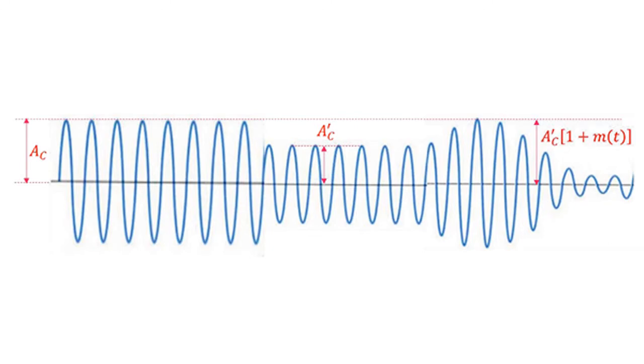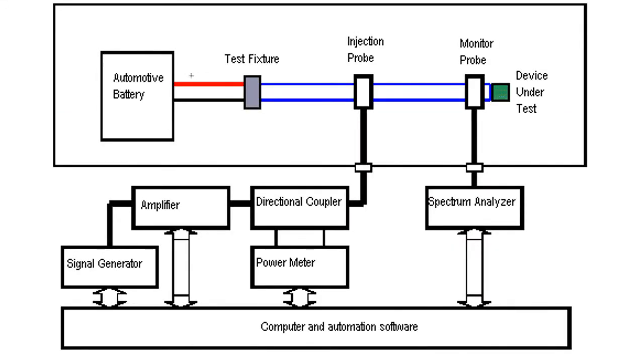The reduction in the peak amplitude of the original unmodulated signal can also be described in terms of the mean power. Thus, to adjust the amplitude of the carrier wave prior to modulation, the power is decreased by 5.1 decibels and then the amplitude modulated signal is added. Until now we discussed about the calibration method used in conducted immunity tests.